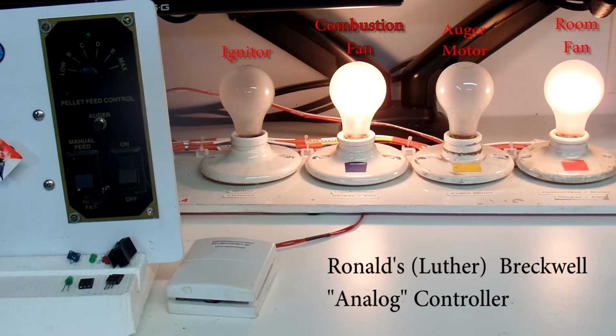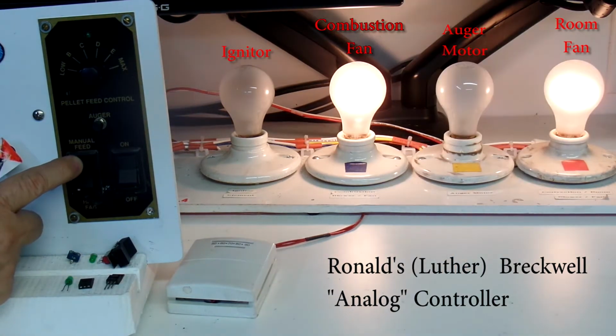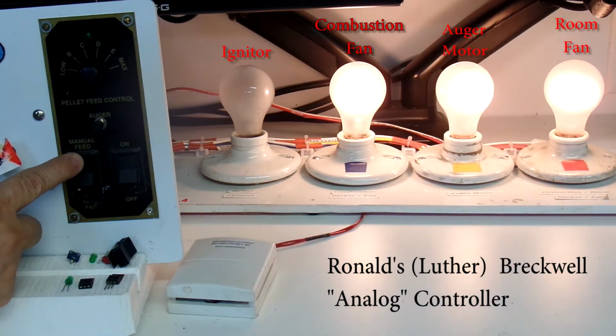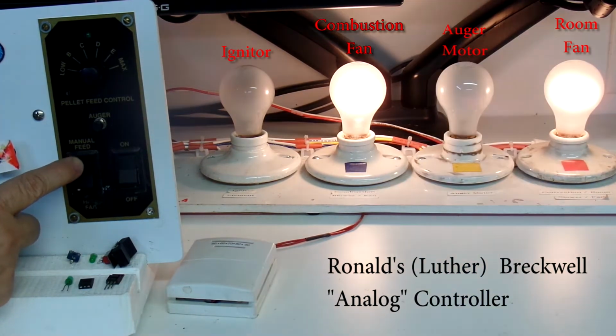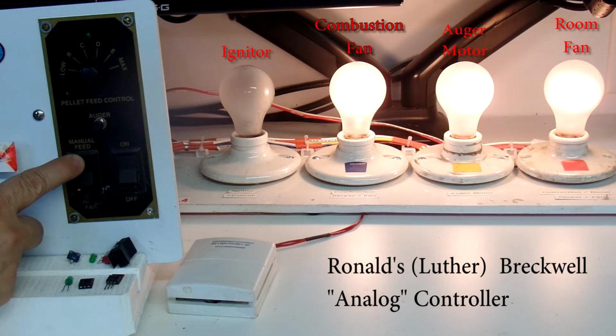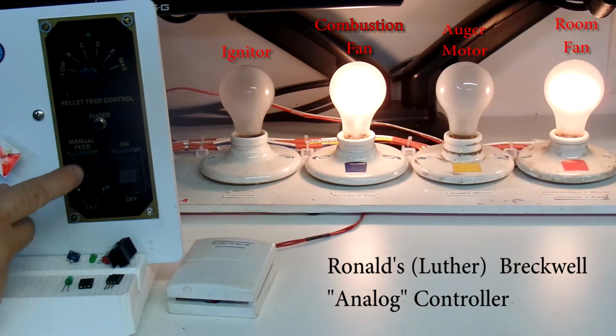The other thing I can do is check the auger drive. I pressed a manual feed and we see that the light at the back has come on, so the auger motor is being driven. We also hear it, the auger motor itself, and we see the X marks the spot decal down here spinning. So that is functioning quite nicely.